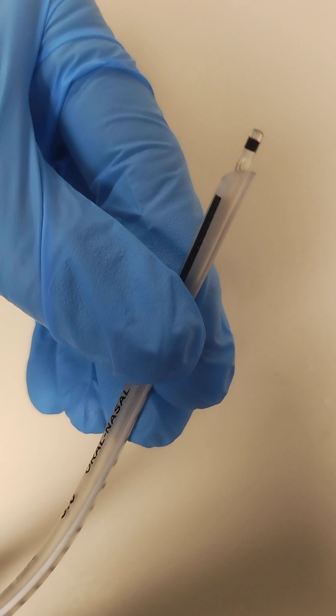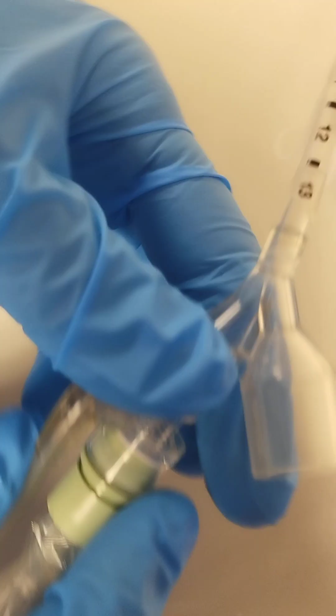Option 2, and this is what the manufacturer video recommends on YouTube if you watch that. It's 12.5 plus 5, so 5 is the distance of this Y adapter, 5 centimeters from the tip of the adapter to here. So what they recommend is you add 5, so we've got 17.5. When we go to our catheter, there's 17, and 17.5 would be the purple. And so you want to see the purple in what they call the manifold, that little window where this plugs in. That's where you're going to look for your purple.